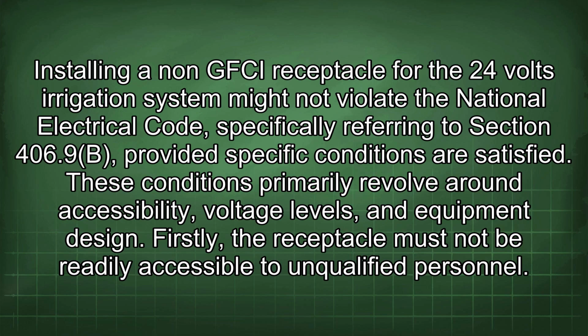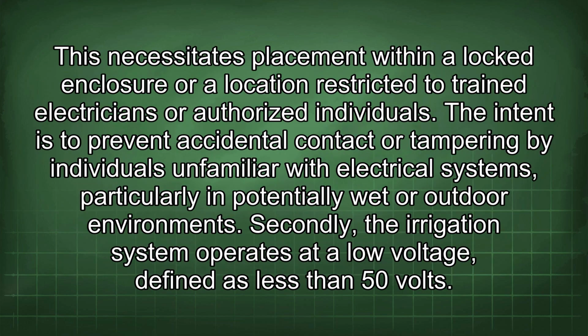Firstly, the receptacle must not be readily accessible to unqualified personnel. This necessitates placement within a locked enclosure or a location restricted to trained electricians or authorized individuals. The intent is to prevent accidental contact or tampering by individuals unfamiliar with electrical systems, particularly in potentially wet or outdoor environments.